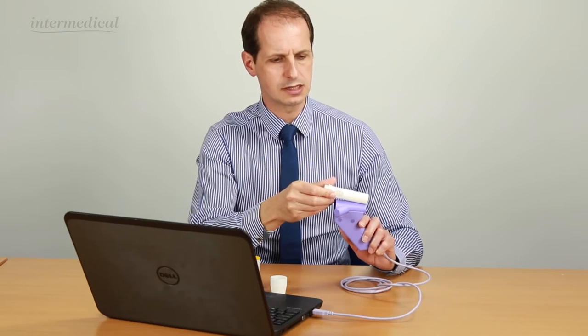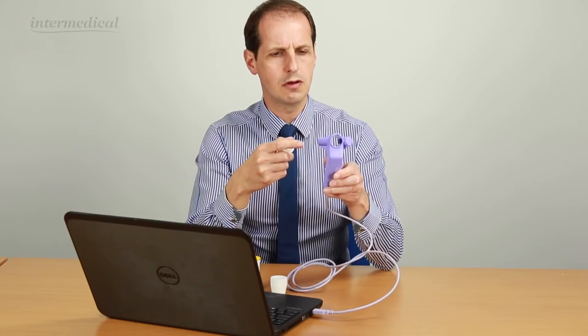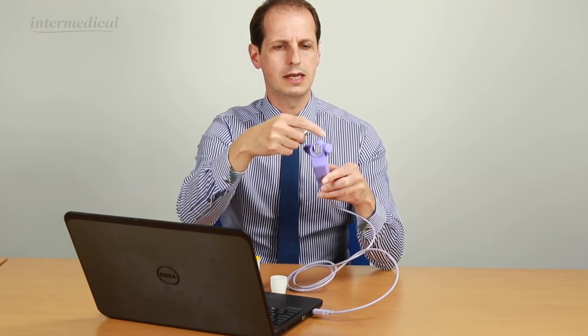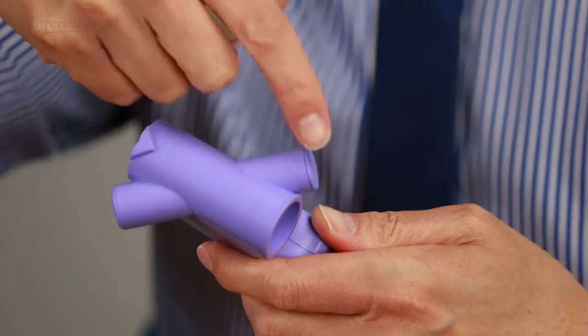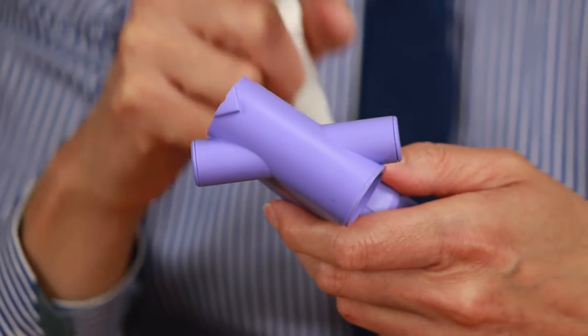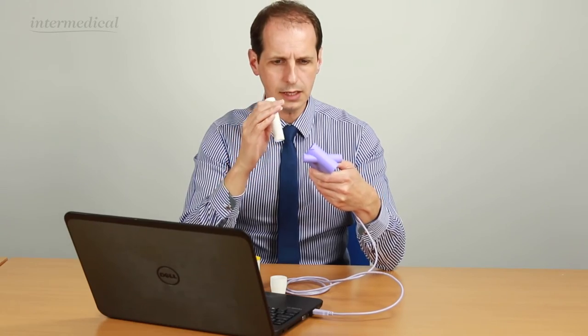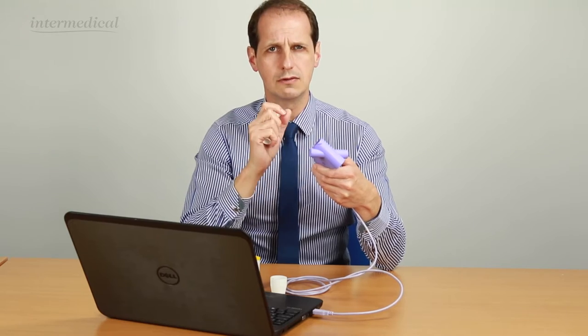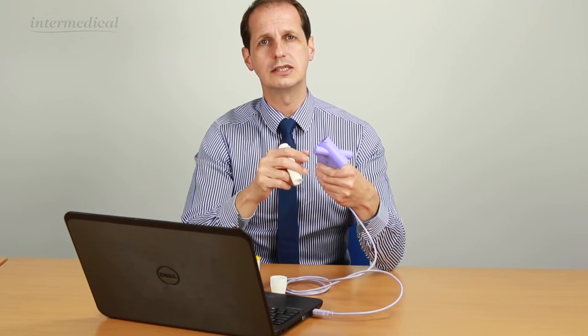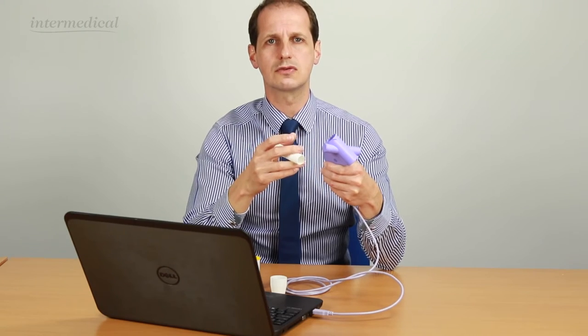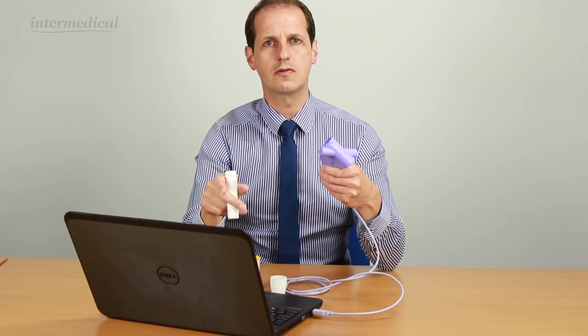So the spirometer itself has three parts to the mouthpiece. So this one is called a Spirette, and this piece goes into the device itself. Now, the device is ultrasonic, so it has zero moving parts in here, and it bounces sound backwards and forwards across a set distance, about 200 times a second. And because this distance is set, the calibration of this cannot alter. Now, within guidelines in the UK, it recommends that you verify this before each clinic. So you can do that with a 3-litre syringe and the results will be stored into the software.